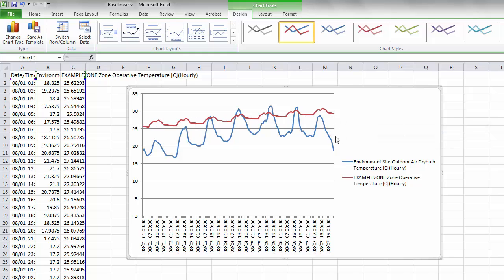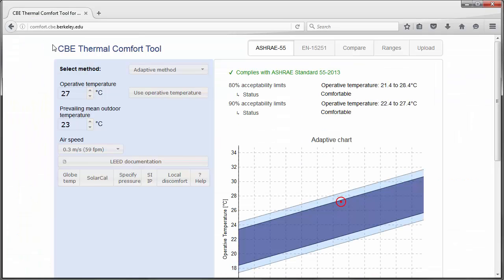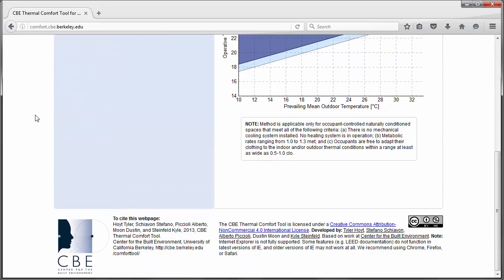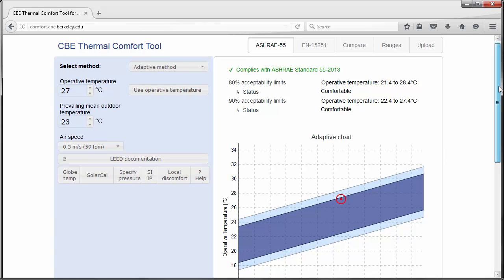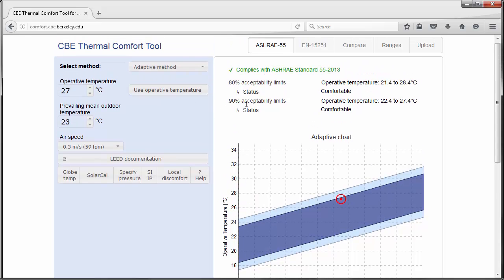Let's place a comfort zone on this graph to see where our indoor temperature falls inside or outside the comfort range. To determine which temperatures to use, we can refer to the Center for the Built Environment's thermal comfort tool. The CBE is a research group at the University of California at Berkeley, and on their website they have a plot for adaptive thermal comfort ranges. I looked at the previous month for our analysis period, and the average was about 23 degrees Celsius. Inputting this prevailing mean outdoor temperature, we can determine our comfort range. At 90% acceptability, the operative temperature comfort range falls between about 22 and 27 degrees Celsius.